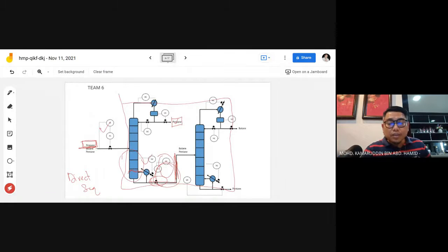Okay, that's about why you cannot have the flow control in the middle, unless this one is not there. If you don't flow control this, then you may have a problem here, because this will determine your product and your capacity. So it's not recommended for you to have a flow control here at the bottom. So the bottom of the first column, okay, clear, right?